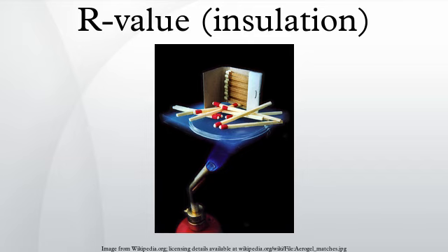Primary role. The R-value is a measure of an insulation sample's ability to reduce the rate of heat flow under specified test conditions. The primary mode of heat transfer impeded by insulation is conduction, but insulation also reduces heat loss by all 3 heat transfer modes: conduction, convection, and radiation. The primary means of heat loss across an uninsulated air-filled space is natural convection, which occurs because of changes in air density with temperature. Insulation greatly retards natural convection, making the primary mode of heat transfer conduction.